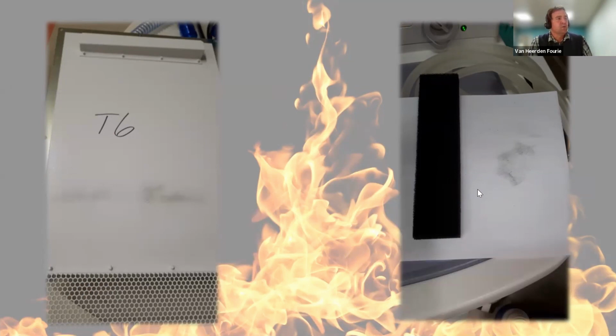When we had a look at the anesthetic machine from the other theater where there was evidence of soot ingress, looking at the filter we could clearly see dark material. An easy quick test to differentiate soot from dust: dust is granular and dry, while soot, if you rub it between your fingers, is like an oily, sticky substance that's difficult to clean off.